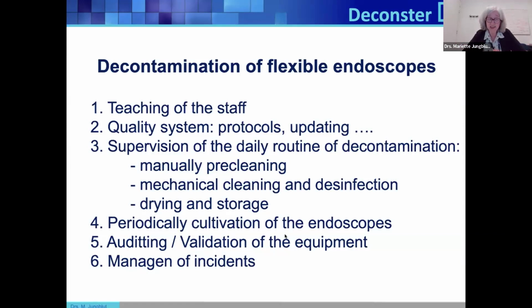Drying and storage is the next thing. Without that, the endoscope is not dry. We only clean, we only disinfect, we do not sterilize. There are still some microorganisms left in this endoscope, whether we like it or not. We have to dry it. And dry doesn't mean 1 drip, 2 drips, 3 drips. 1 drip is wet. Dry is no drips. And we have to take our time as well. That's why I think it has to be a mechanical drying as well.